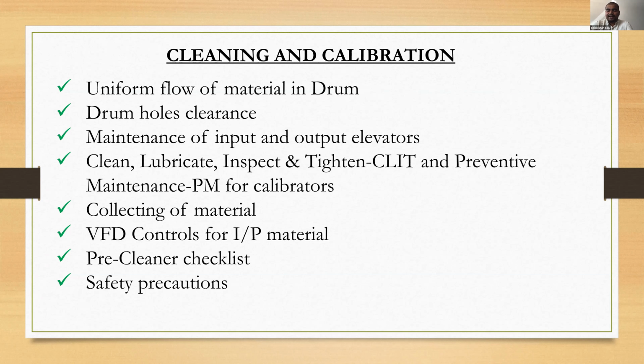Uniform flow of material in the drum - in the calibration system there is a drum and an input conveyor or screw conveyor. While the drum is rotating, the material flow should be uniform. If you put 10 bags at a time and then just one bag, the load becomes uneven, and most of the material will go for the next sections only. For that, we have to use VFD drives - variable frequency drives - which give uniform flow. Then there is not much possibility of mixing ratios.